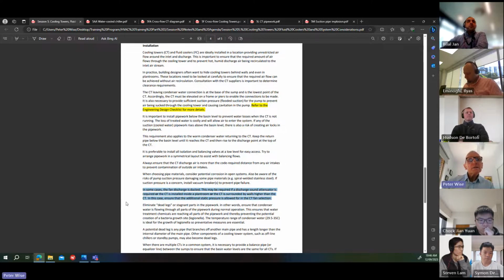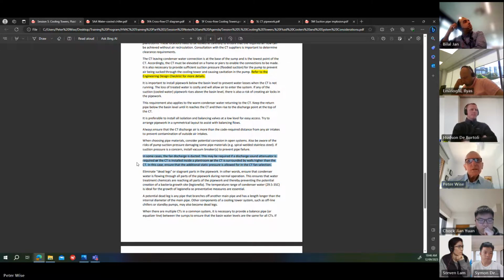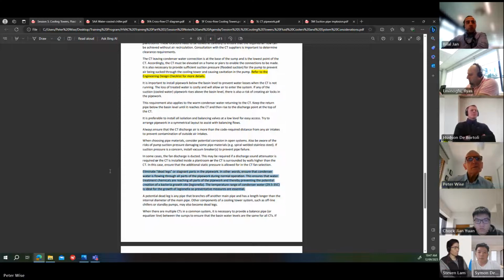In some cases, the fan discharge is ducted. This may be required if a discharge sound attenuator is required, or if the cooling tower is installed in a plant room, or if the cooling tower is surrounded by walls higher than the cooling tower. So as I said before, you want to get that discharge up above any walls. So you have to ensure that the additional static pressure is allowed for in the cooling tower fan selection. So in other words, you need to tell the cooling tower supplier that you've got additional static required on the discharge, and they'll select the fan accordingly. If you don't allow for that extra static pressure, the fan selection won't be good enough, won't have enough pressure, and then that will affect the performance of the cooling tower because you haven't got enough air flowing through it. So all these things are important.